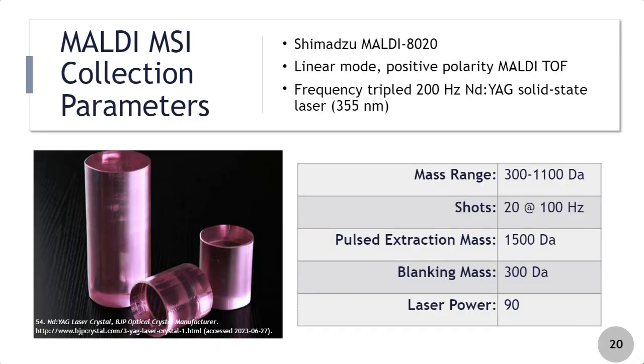For our MALDI acquisition, the MALDI-8020 is a linear positive-polarity-only MALDI-TOF instrument incorporating a frequency-tripled Nd:YAG solid-state laser with a wavelength of 355 nm and a maximum frequency of 200 Hz. For our experiments, we used a mass range of 300 to 1,100 Daltons, collecting 20 shots at 100 Hz, using a blanking mass of 300 and a relative laser power of 90. We used that consistent relative laser power across all samples to provide consistent ionization rather than optimizing for each individual sample.